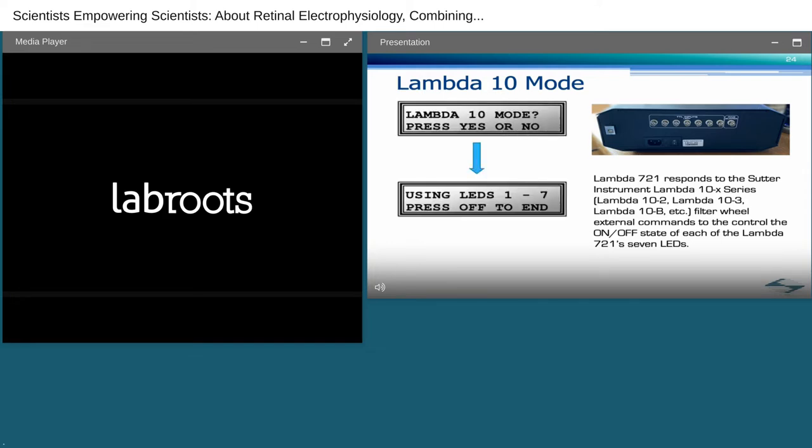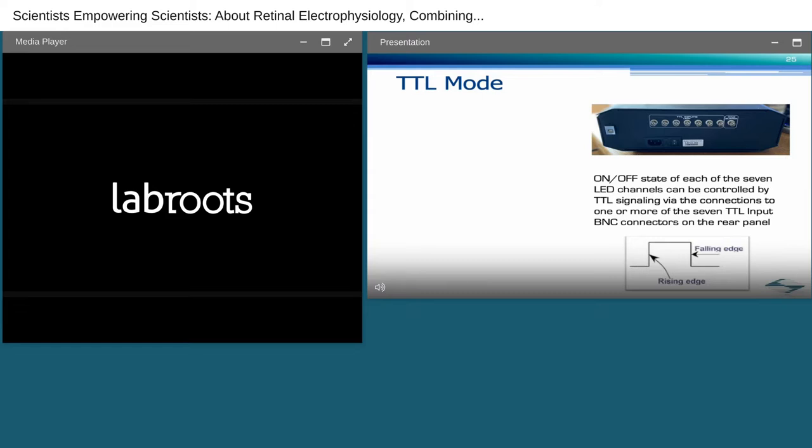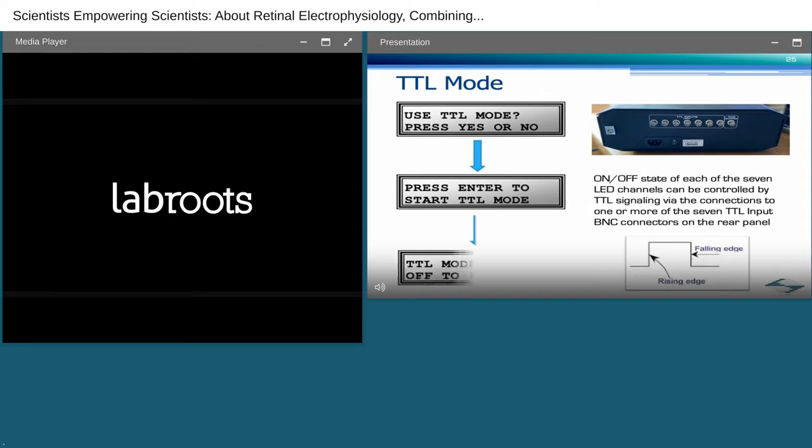This mode allows imaging software, for example, Micro-Manager that already has support for our Lambda 10X controllers to interface with the 721 without the need of any software changes. To activate this mode, first, if another mode is active, press off to return to menu selections. Turn the selection knob until the Lambda 10X prompt appears. Press the Yes button, which will display the mode's execution prompt. In TTL mode, the on-off state of each of the seven LED channels can be controlled by TTL signaling via one or more of the seven TTL input BNC connectors on the rear panel. The state of an LED is on when its corresponding TTL input receives a TTL high signal, which typically is an amplitude above 2.7 volts, and is off with a TTL low, which is typically below 400 millivolts.